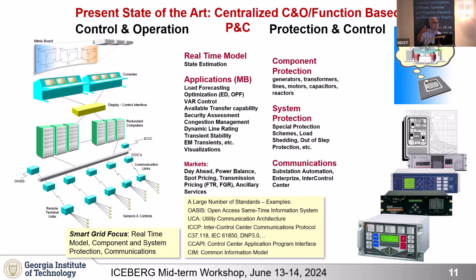So of course, with the merging units, we can go to using the actual capabilities of these merging units in terms of providing data at very fast rates. And we have two standards there. One standard is 80 samples per cycle. So this means the rate is different for the United States and Europe because the standard is based on a cycle. And also another standard, it is 256 samples per cycle. Okay? And therefore, when we use merging units, the SCADA comes in at these rates. Okay?